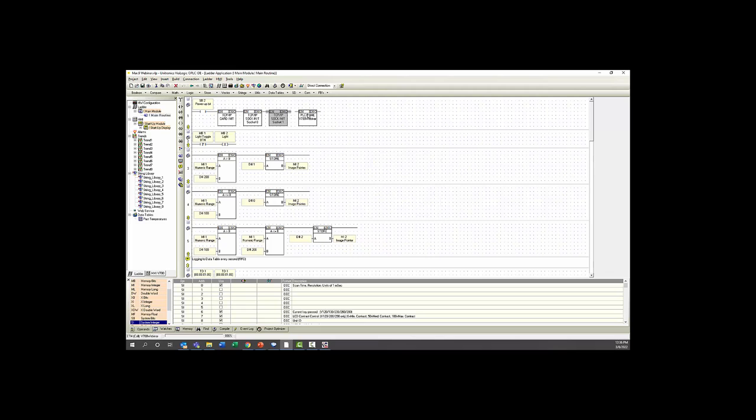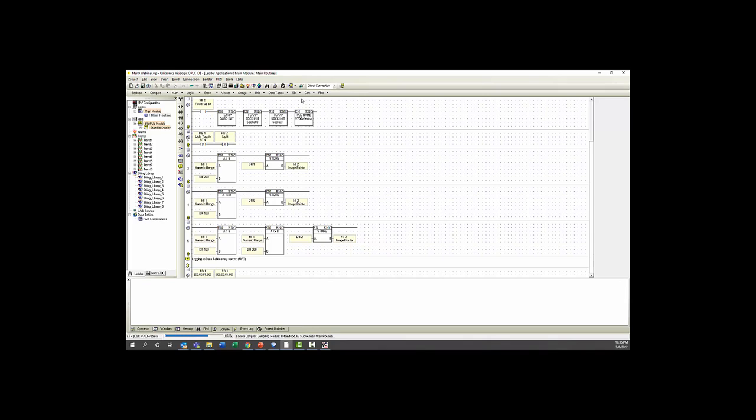And because we have connection, we can also remotely download to our PLC. When you're doing this, you would want to make sure that you haven't edited your IP address in any way, because otherwise you may not be able to connect to it if that IP address is already taken. Another little tidbit is that downloads are typically a little bit faster over Ethernet than they would be with a standard USB connection. Now that we have this set up with these two sockets, we can go online here, and we'll leave that in online mode while we go to our data export tool.